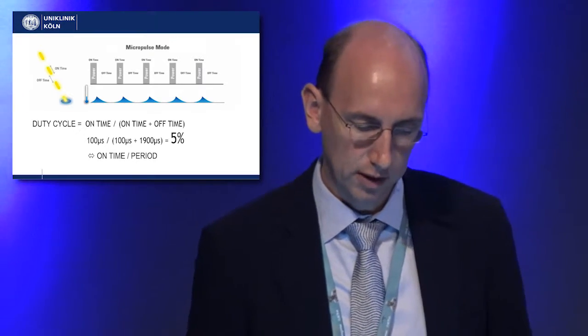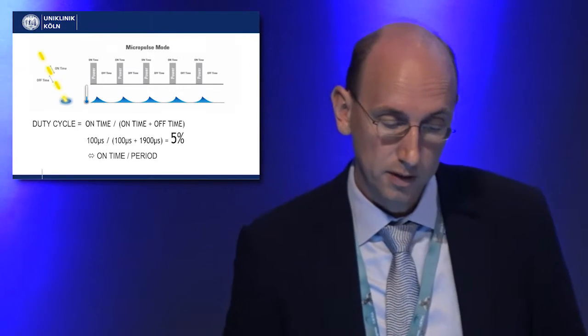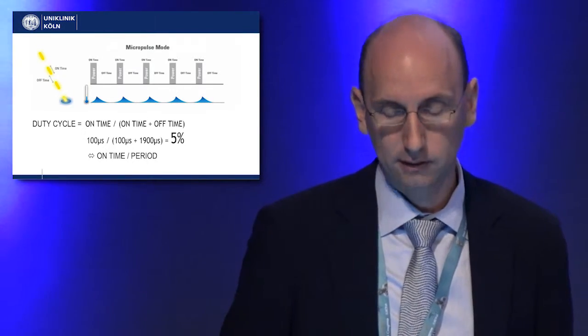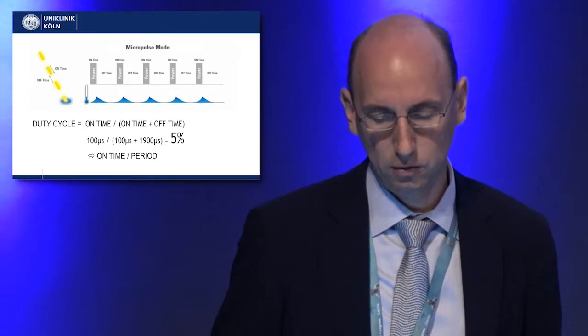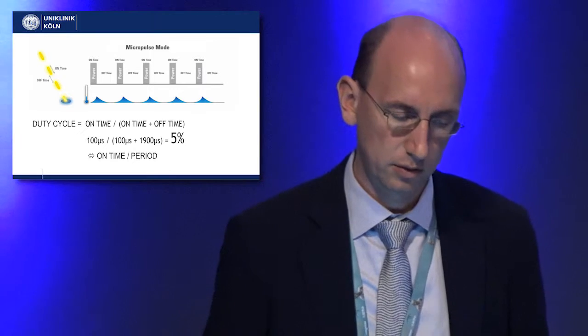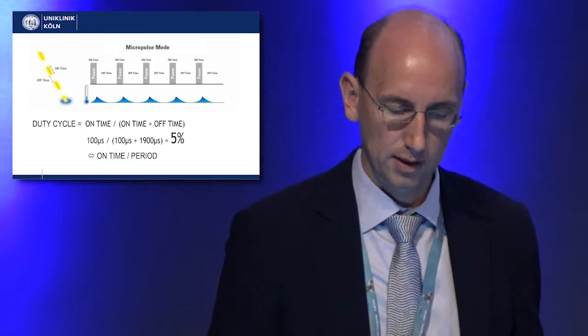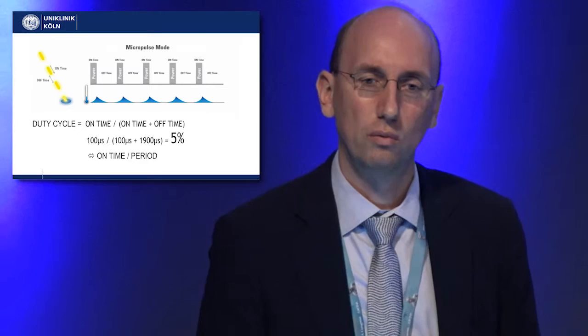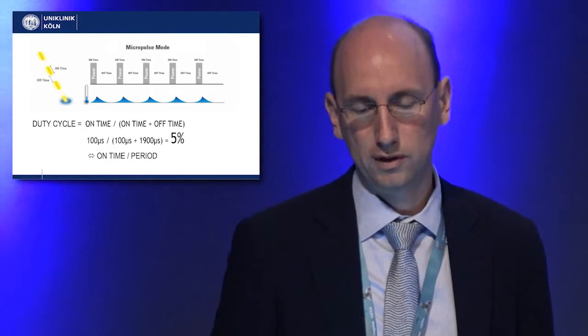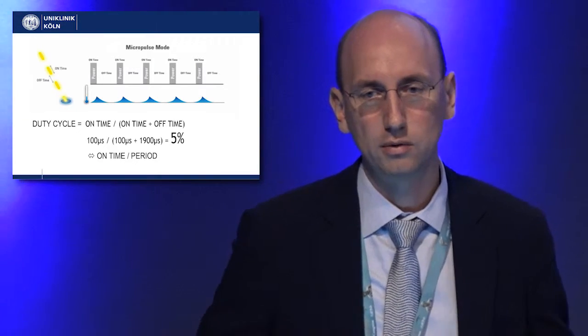With MicroPulse you will also come across the term duty cycle, which is basically the time the laser is on in a given period divided by the time it is off. For safety reasons, we currently apply a duty cycle of only five percent. That means the laser is on for 100 microseconds and then off for 1900 microseconds — a long time for the tissue to dissipate all the heat.